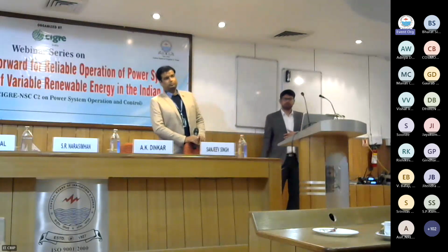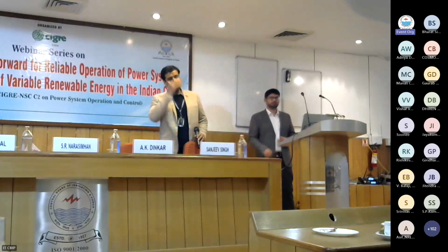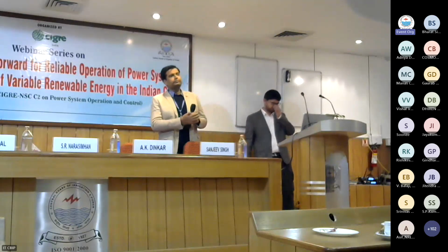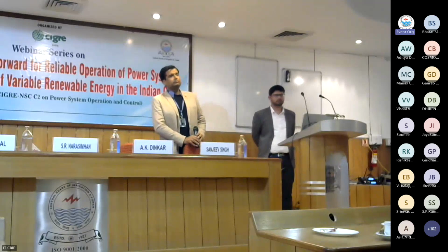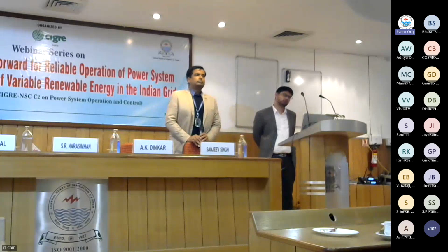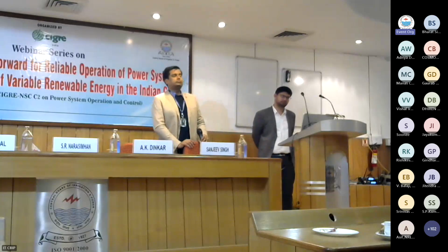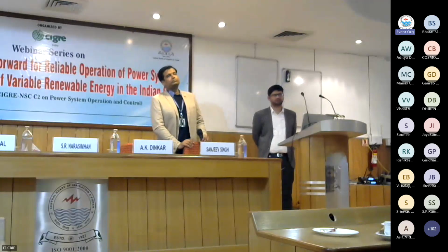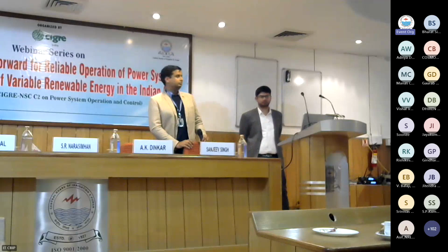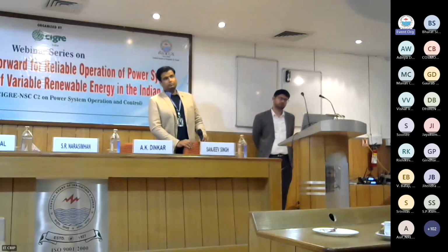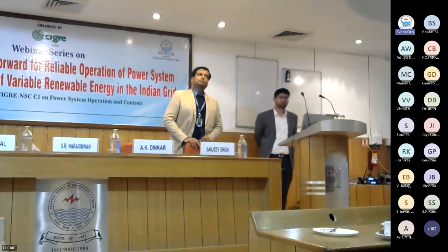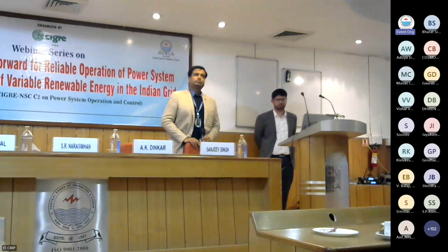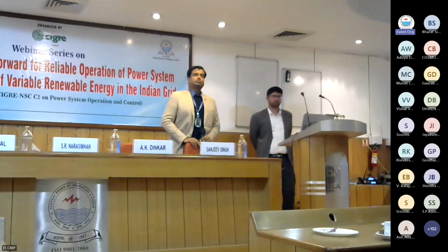Just to add on that, I have done some power quality studies in one of my R&D labs, and I was really surprised by the type of data I got. It was bewildering. Everything looks fine, like in this room, but if you put the three-phase analyzer and PQ analyzer and look at the different parameters available, even harmonics were there, and negative sequence harmonics and many complicated things. What was the load in my room? That got me thinking, because it is something we cannot visualize easily. Only measurements from the PQ meters can do that.